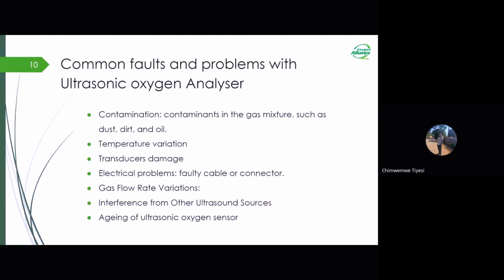All right, now we'll move on to look at the common faults and problems with ultrasonic oxygen analyzers. Ultrasonic oxygen analyzers are used for measuring oxygen concentration in various environments, be it in hospitals or industries. Of course, our main emphasis is on medical use. While these analyzers are generally reliable, they can experience common faults and problems, just like any other analytical equipment. Some typical issues that may arise include sensor contamination. Contamination is a main issue that can affect the accuracy of the readings on oxygen analyzers.